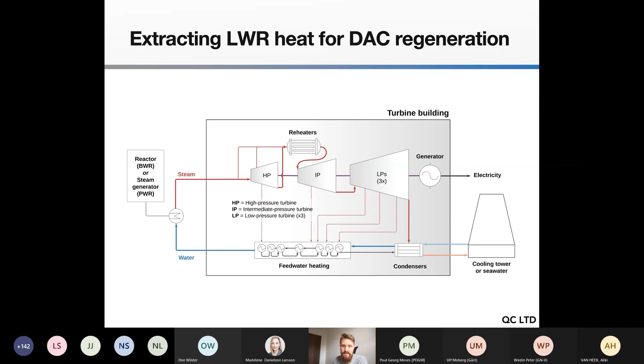So what is interesting from an economical standpoint here is how much electricity we are losing by doing this. If we want to tap into a steam pipe here and extract some of that steam with a valve to an external heat exchanger, that steam that we took away from this cycle could have gone through all of these turbines and imparted more energy to the turbine blades and made more electricity. A rough way to calculate this is just to see how much electricity that steam you extracted could have made, and that becomes the opportunity cost of doing this extraction. So a simple equation for this is written here.